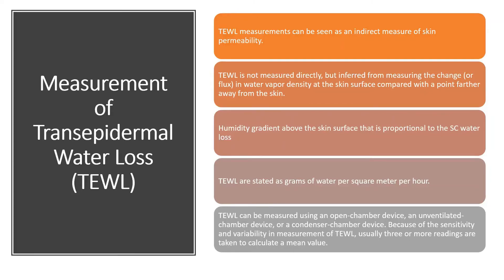The humidity gradient above the skin surface is proportional to stratum corneum water loss and is stated in terms of grams of water per square meter per hour. It can be measured using an open chamber device, an unventilated chamber device, or a condensing chamber device. Because of sensitivity and variability in TEWL measurements, three or more readings are taken to calculate a mean value.